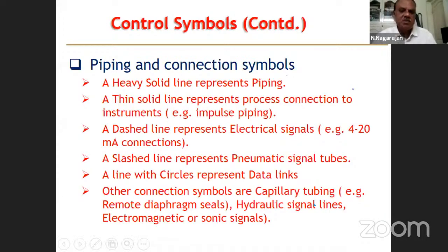So piping and connection symbols, which we have seen already. Heavy solid line represents piping. Thin solid line shows the process connection to the instruments. That is, a pressure gauge is mounted on the line, a thin solid line. That is called impulse piping. A dashed line, which I have already explained, is electrical signals. Example, 4 to 20 milliampere signals. Slash line represents pneumatic signal where instrument air is going. Line with circles gives you data links. Other connection symbols are capillary tubing, example, remote diaphragm seals, hydraulic signal lines, electromagnetic or sonic signal lines, okay, which we have seen already.